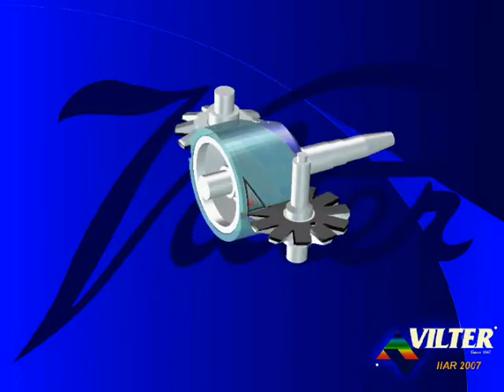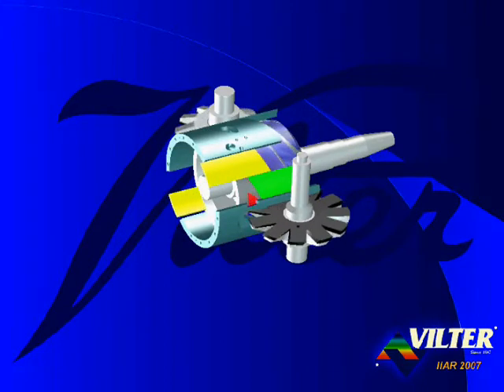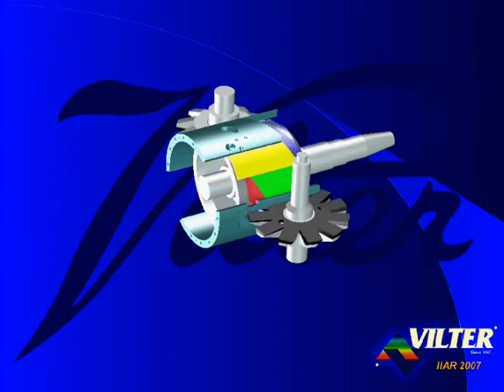Rather than fixed discharge ports, the Vilter single screw has parallel slide valves, infinitely variable capacity, and infinitely variable volume ratio slide valves for peak efficiency at any capacity.